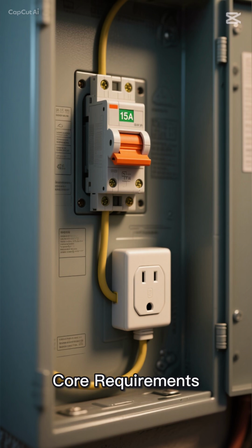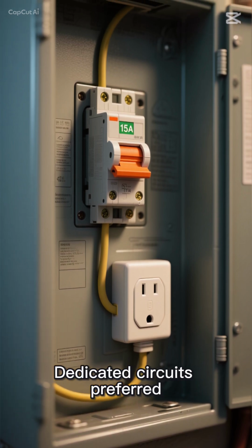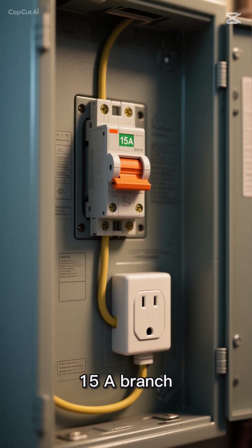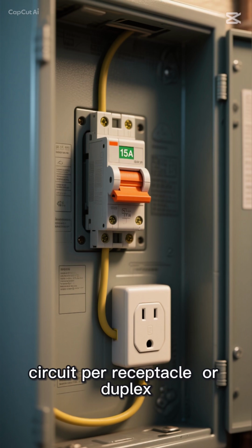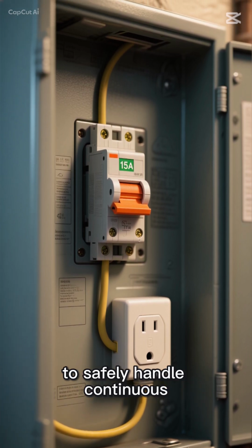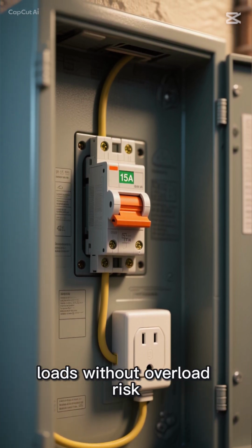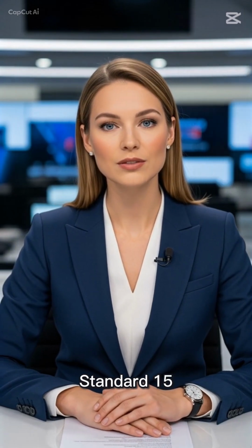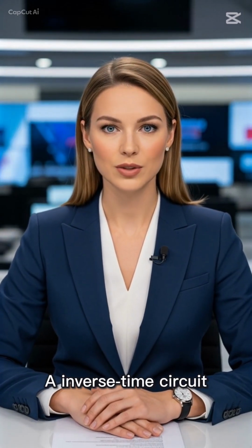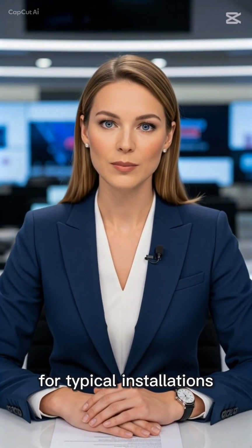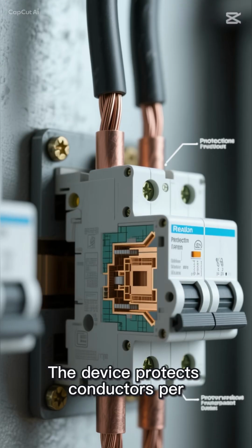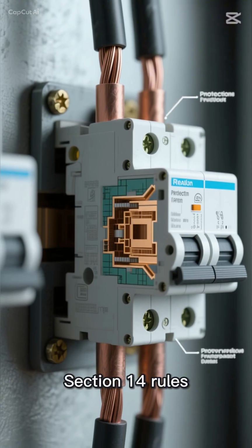Core requirements. Dedicated circuits preferred. Most setups use a dedicated 15A branch circuit per receptacle, or duplex, to safely handle continuous loads without overload risk. Overcurrent device: standard 15A inverse time circuit breaker, or fuse, for typical installations. The device protects conductors per Section 14 rules.